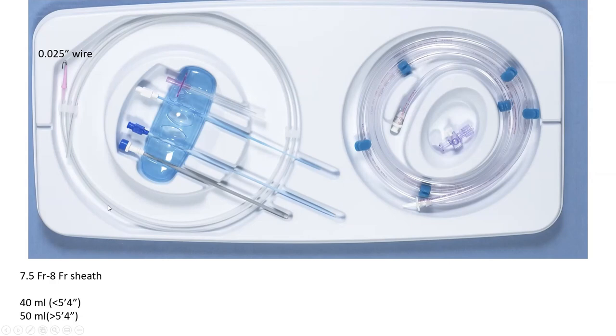Then you have that part, which are the sheath and the wire. So you have the 8-French sheath, and it's typically for patients less than 5'4 in height, you use a 40 milliliter balloon through a 7.5 French sheath. For over 5'4 in height, it's a 50 milliliter balloon through an 8-French sheath. So this is the sheath, and this is the wire. Now, this wire is for advancing the balloon pump. It's that 0.025-inch wire.